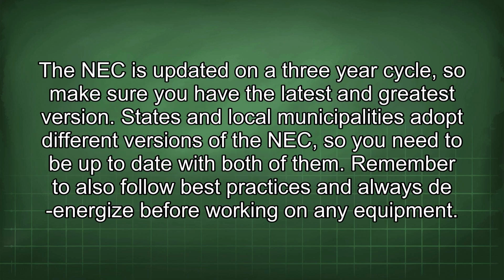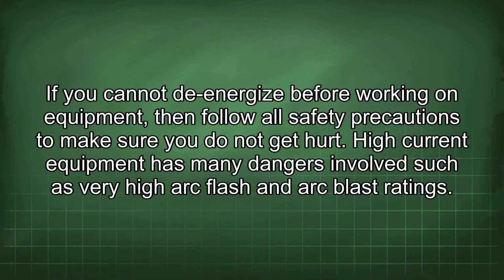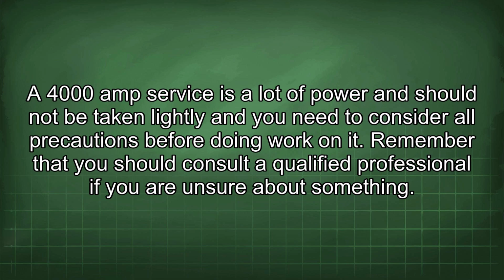The NEC is updated on a 3-year cycle, so make sure you have the latest and greatest version. States and local municipalities adopt different versions of the NEC, so you need to be up to date with both of them. Remember to also follow best practices and always de-energize before working on any equipment. If you cannot de-energize before working on equipment, then follow all safety precautions to make sure you do not get hurt. High current equipment has many dangers involved, such as very high arc flash and arc blast ratings. A 4000 amp service is a lot of power and should not be taken lightly, and you need to consider all precautions before doing work on it.